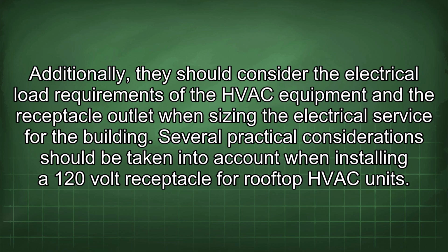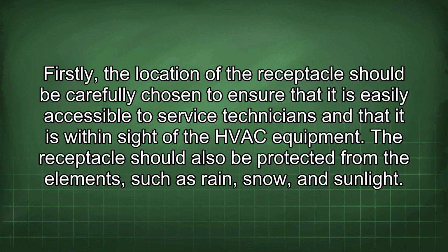service for the building. Several practical considerations should be taken into account when installing a 120-volt receptacle for rooftop HVAC units. Firstly, the location of the receptacle should be carefully chosen to ensure that it is easily accessible to service technicians and that it is within sight of the HVAC equipment. The receptacle should also be protected from the elements such as rain, snow, and sunlight.